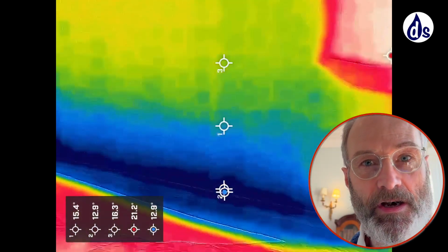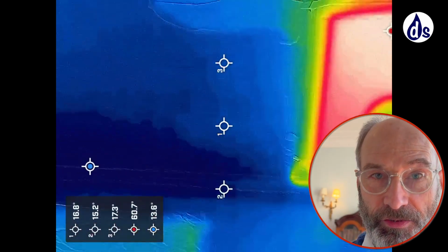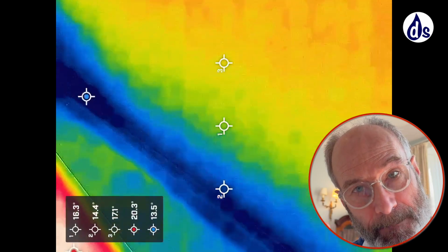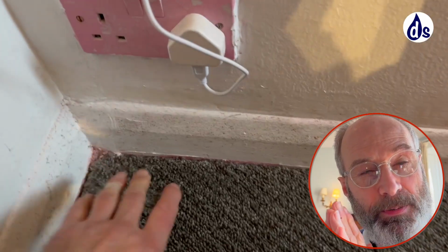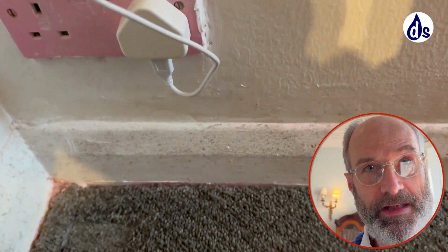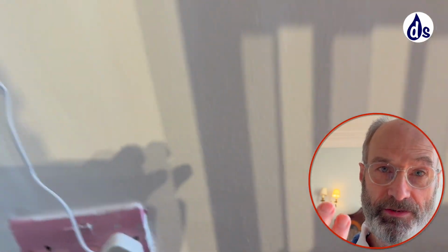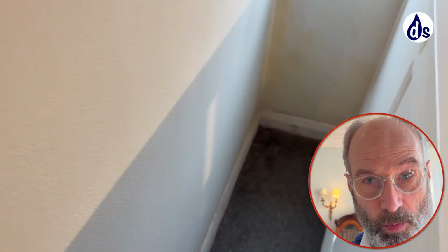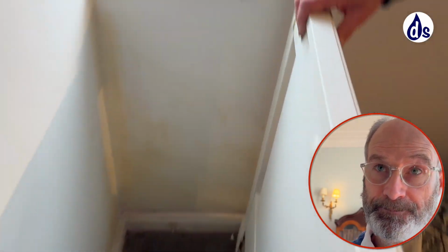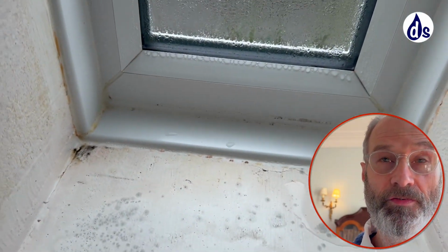Now I go into flat 1, and you can see from my glasses that it was high humidity, and it wasn't especially cold during that day. Looking through the thermal imaging camera, you can see all the zones of heat loss, but they're an explanation for why you get damp in certain areas, but the root cause is the excess vapour. Notice the heat loss at the base of the wall. That's because of the garage, the metal, but also condensation causes the water to dampen brick, which is a poor insulator. So there was dampness across the whole of that wall.